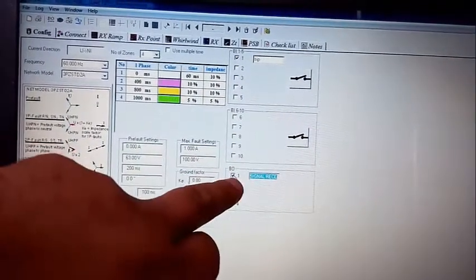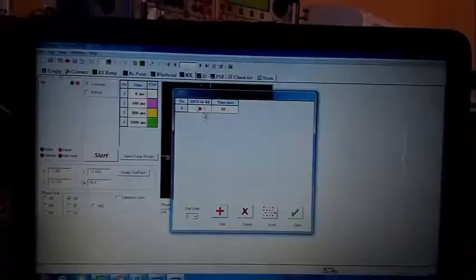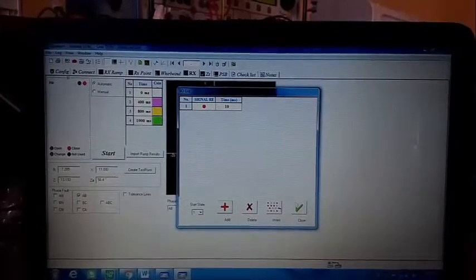This binary output is used as a carrier signal. Binary output number one is set from normally open to close, used as a carrier signal for the relay to make a trip. When this binary output is red, it means a signal is received. After a delay of 10 milliseconds, the relay will take action. After injecting, the value shows zone number one.